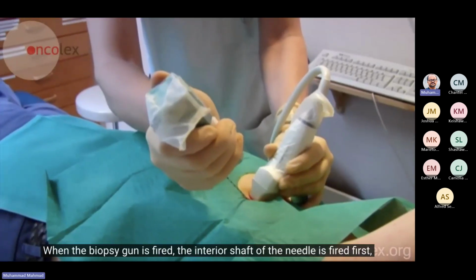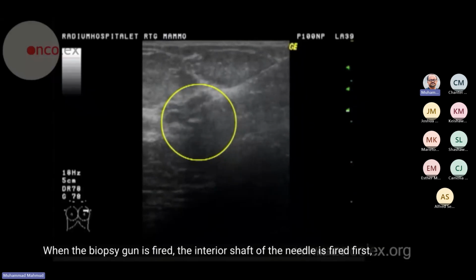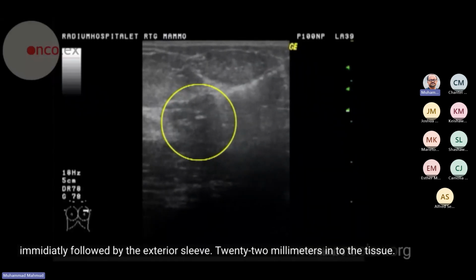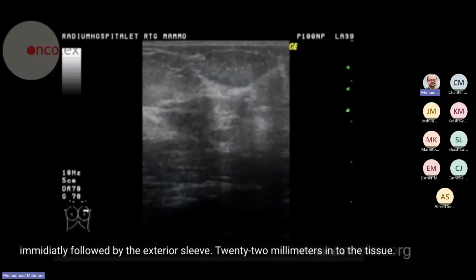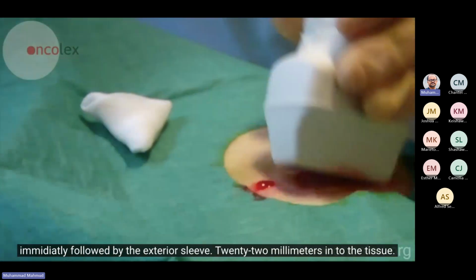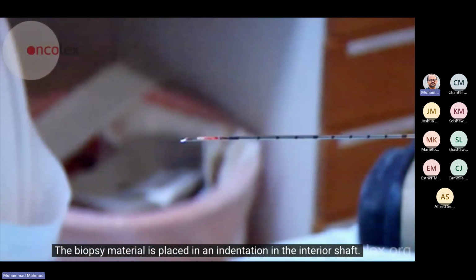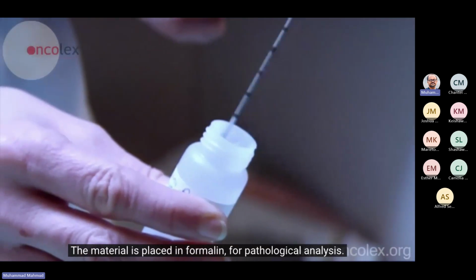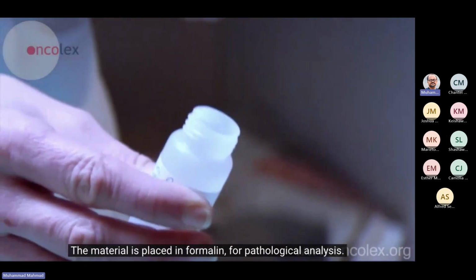When the biopsy gun is fired, the interior shaft of the needle is fired first, immediately followed by the exterior sleeve, 22 millimeters into the tissue. The biopsy material is placed in an indentation in the interior shaft. The material is placed in formalin for pathological analysis.